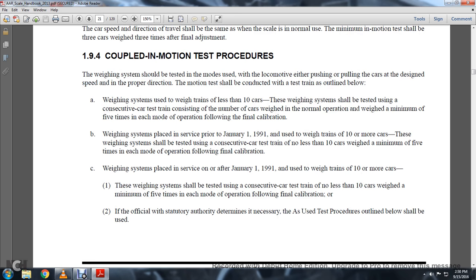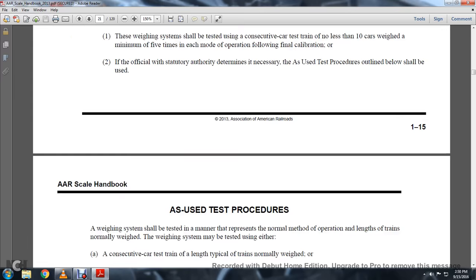The weighing system placed in service prior to January 1st, 1991, used weight trains of 10 or more cars. The weighing system should be tested using a consecutive car train of not less than 10 cars, weighed a minimum of five times in each mode of operation following the final calibration. If the official statutory authority determines it necessary, the test procedure outlined below shall be used.